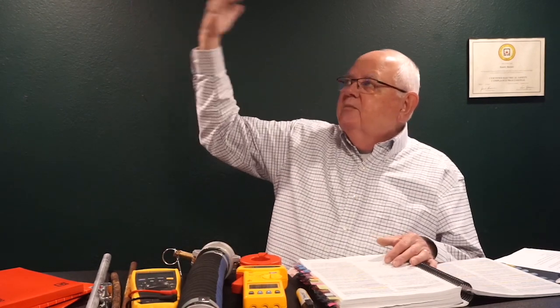So why would we want to connect an electrical distribution system to the ground? The reason is, it tells us in 250.4, two reasons. Number one is we want to limit voltage surges. Worst case scenario I can think of is a lightning strike. If I have a big lightning strike somewhere and it hits my building and wants to come into this little studio here or whatever and destroy all of my electronic equipment and everything else, I don't want that to happen.